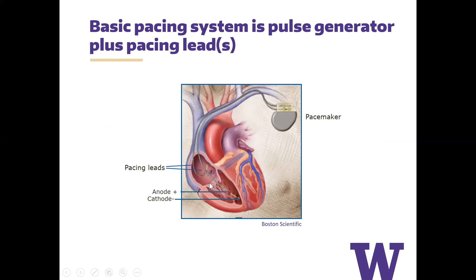So how does the circuitry run? You go from the battery, which is typically now lithium iodine, and it sends an electrical impulse via the pacing lead to the cathode, which is the tip electrode. That impulse travels to the myocardium. The impulse then travels through the body, tissue, and fluid, and then returns to the anode, which is the ring electrode for bipolar systems. In unipolar systems, the anode would just be your pacemaker generator.